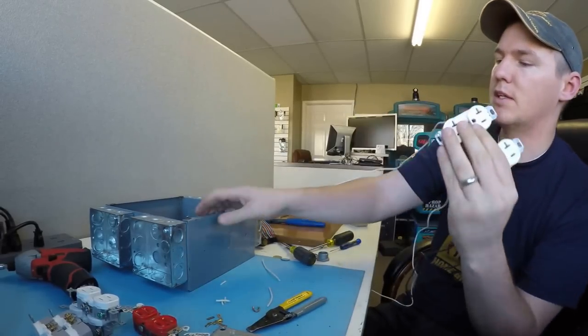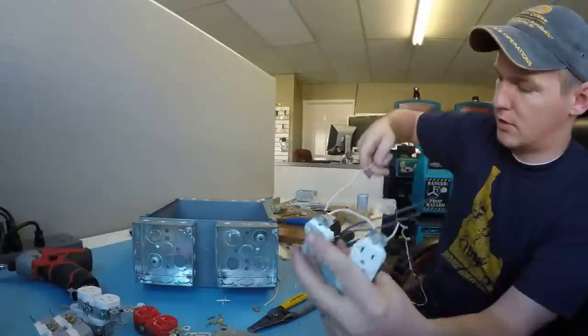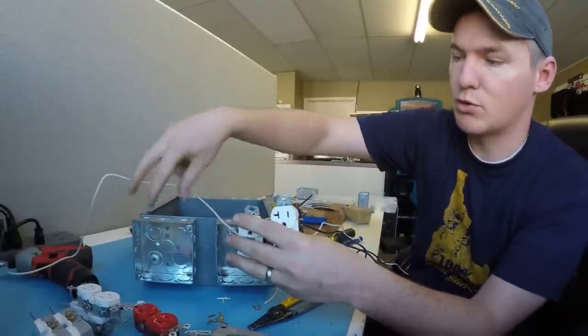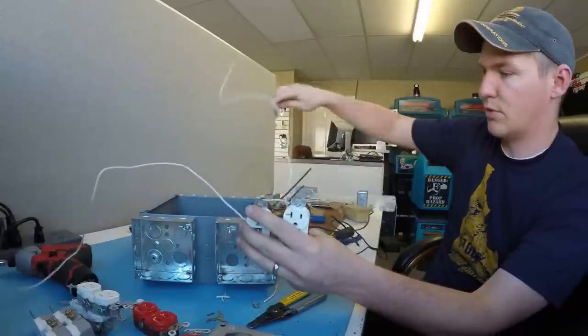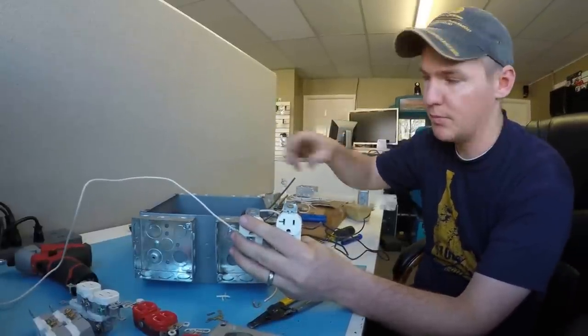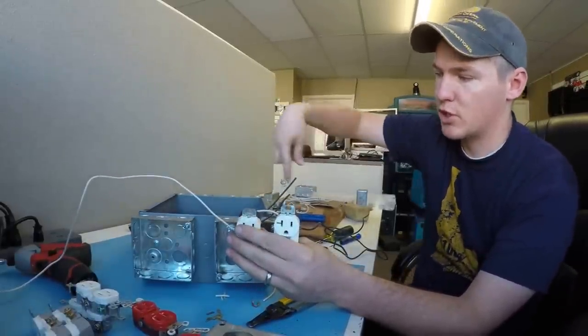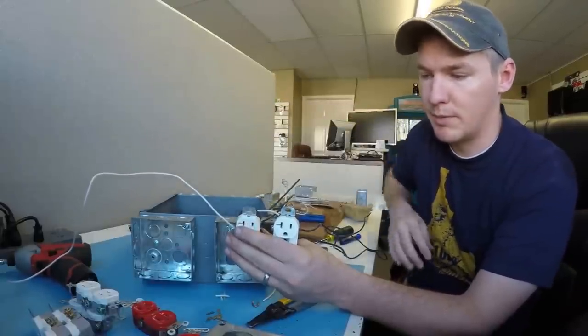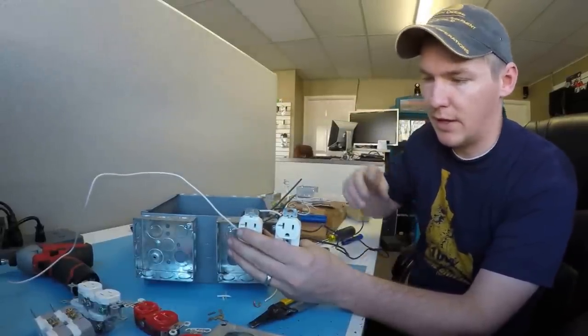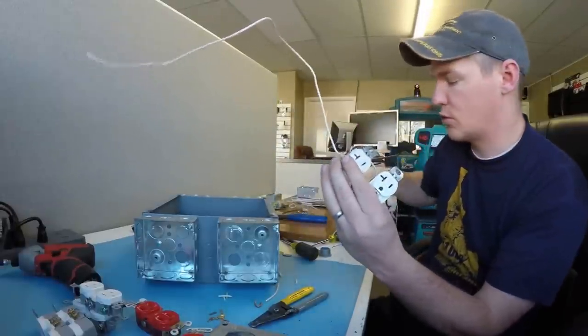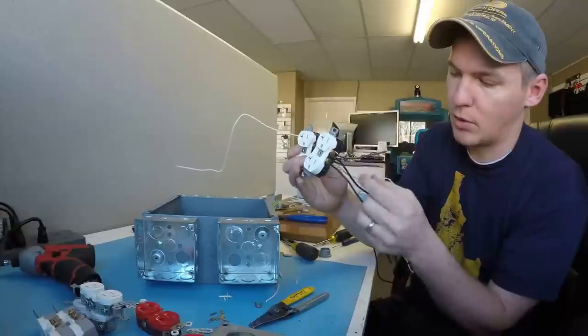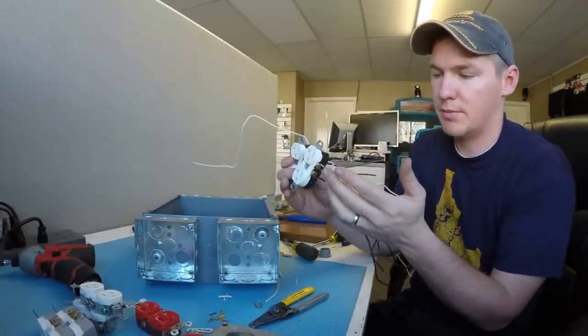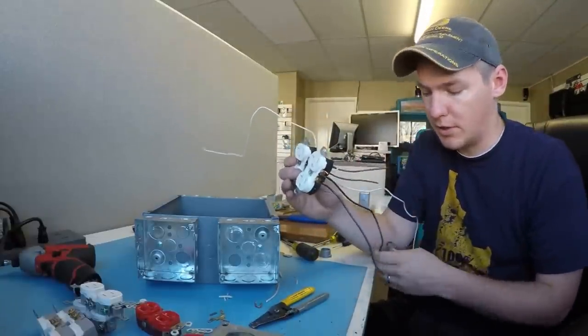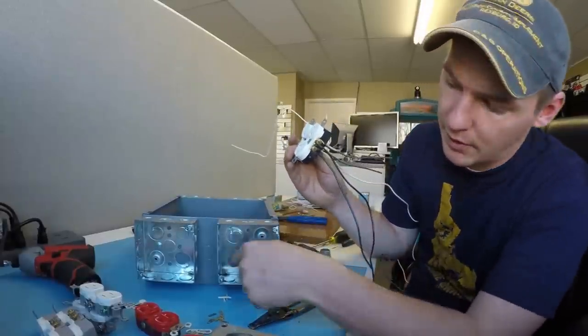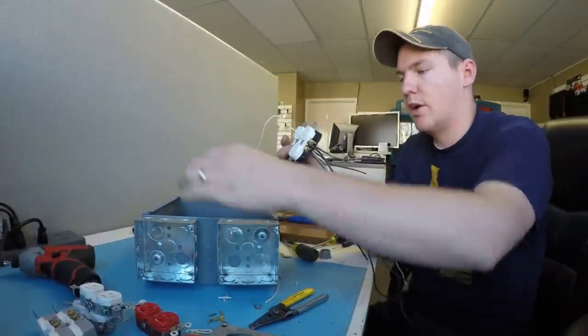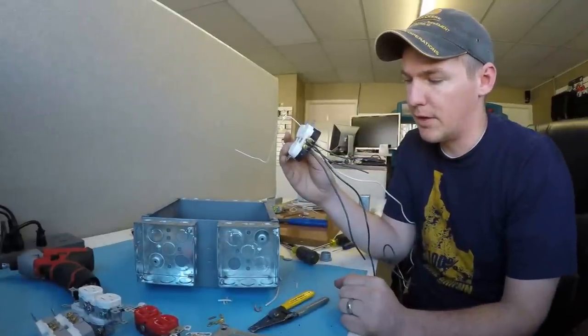And what that's going to be is tying this box. This one's going to go over and provide neutral power for that box. This one's going to go across and provide neutral power for the box at the bottom. Then that one will tie in. So basically, there's a big chain of white wire connecting every outlet. And the tab's not broken there, so it carries through to every single outlet. Then the blacks, the tab's broken, so every copper screw is gonna have a black wire coming off of it, just going nowhere for the time being. And then I'm gonna drill the hole in this box, put them through there, and they will go into the relay board.